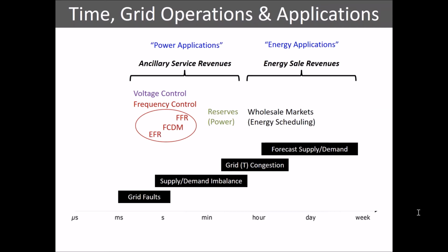Batteries in particular are very fast reacting. So you've seen, certainly here in the UK, that enhanced frequency response has been quite good for battery providers, because batteries can go to their full output in milliseconds, so very quick responding. Battery storage can also play potentially into things like reserves, into slightly longer term coverage of problems.